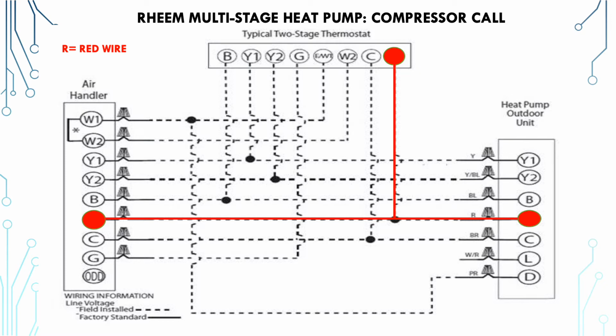Now, the more common thing that they like to do is use the blue wire for the OB run, or in this case on Rheem, it's B, and they like to use brown for common. Yeah, regardless of those colors, you still use the industry standard connections. All right, so in this case, you see that we've got the red wire. So this is the R contact up here at the top for the thermostat. That's your 24-volt call, and it's going to go to R on both the heat pump and the air handler.